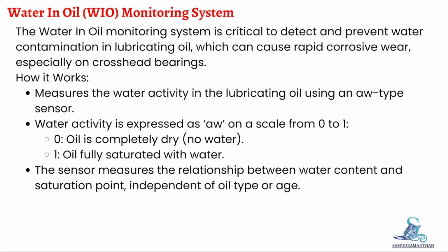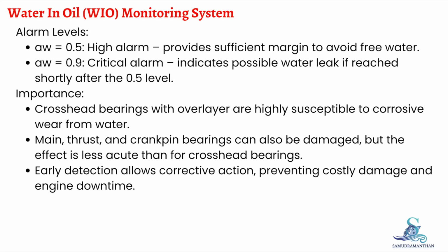Unlike simple water content measurements, this method accounts for the saturation point of the oil so it works reliably regardless of oil type or age. The system uses two alarm limits. At aw equals 0.5, the system raises a high alarm, giving enough time to prevent free water formation. At aw equals 0.9, a critical alarm is triggered, which usually indicates a leak.